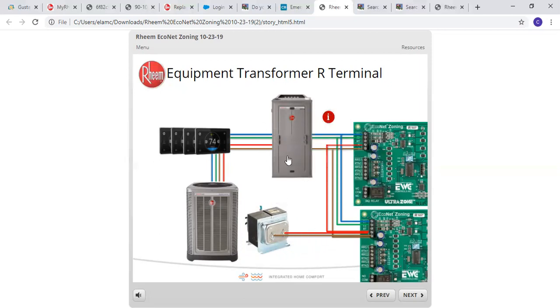So this gives you a kind of a color thing here. We have all of our thermostats, primary and zone stats, on the Econet bus. We're going to come over here and go E1, E2, R, and C. As we go over to zone panel 1, we're going to have E1, E2, common. We're not going to bring that R over here because we're using a secondary transformer.